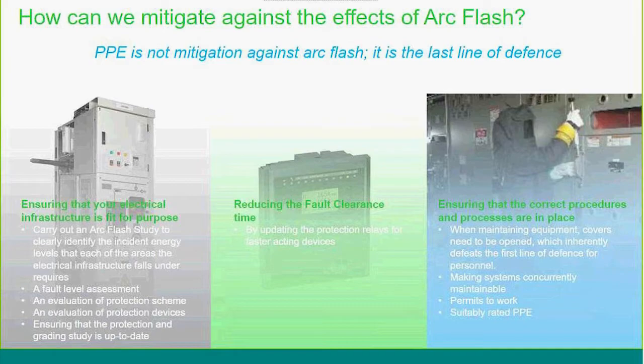Once you have the information, you can make sure your processes are more robust then. You can make sure that the people are kitted up correctly to enter that zone, which could be the highest risk zone of your substations. Make systems concurrently maintainable. Take the risk away from it. Try and make systems that are N+1 so you can make isolation, so you don't have to do maintenance.